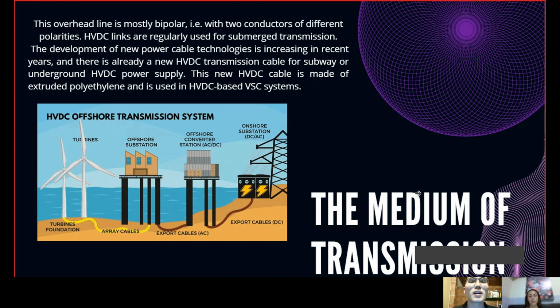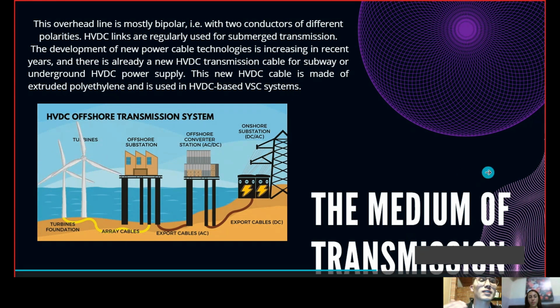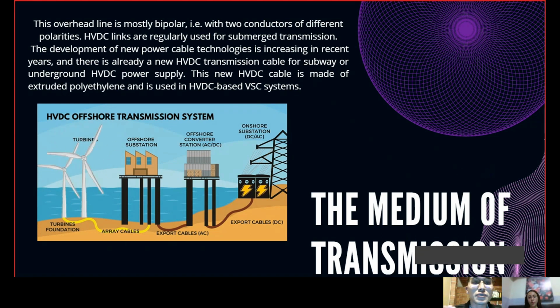The transmission was made by a single cable, thus being more economical. Also, AC transmission is invasive because it uses a tower, and the higher the tension rises, there must be great separation between the cables, and that generates more cost. For DC, the most economical way is to use the sea and land as a return. What is done is to create a voltage with respect to land, and use the land for the current to return to the sea.